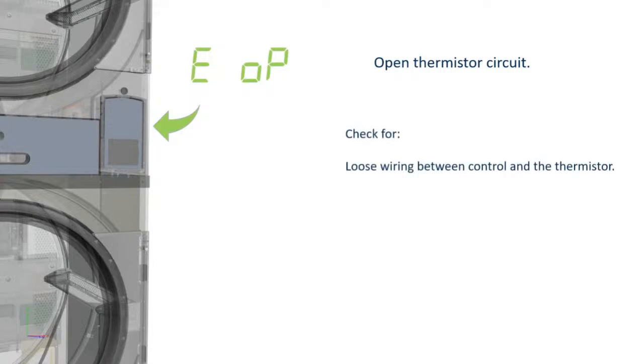Remember, the wires are just as important as the thermistor. So the first thing we look for is, is there loose wiring either on a connector or a terminal somewhere between the control and the thermistor? Let's investigate that - is one of those wires cut or rubbed, something like that? Did we do some mechanical service and not do things quite right?